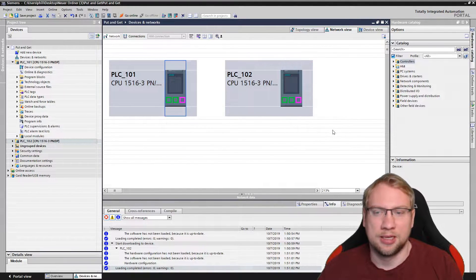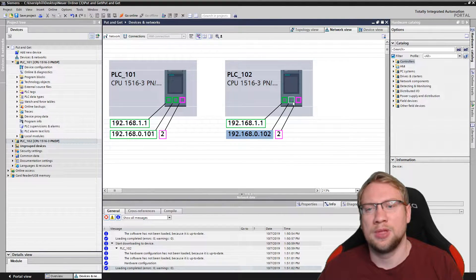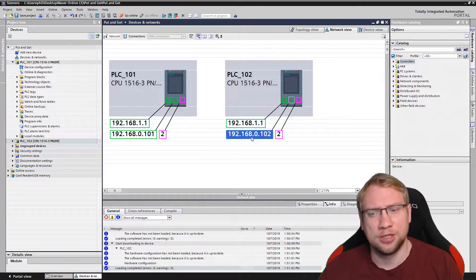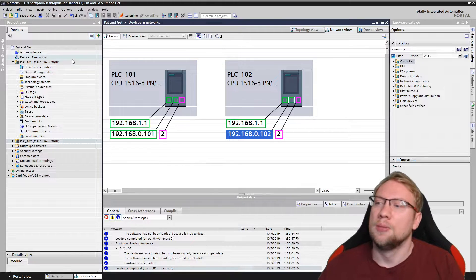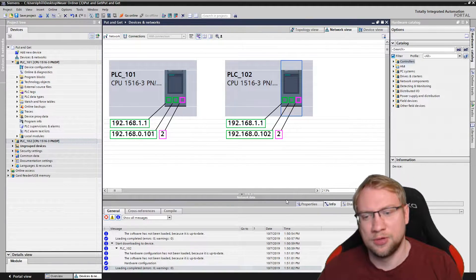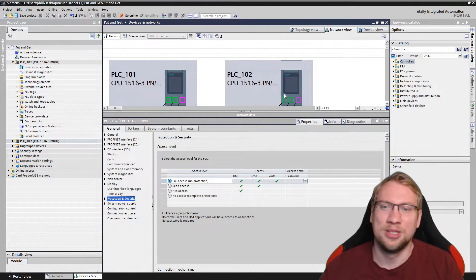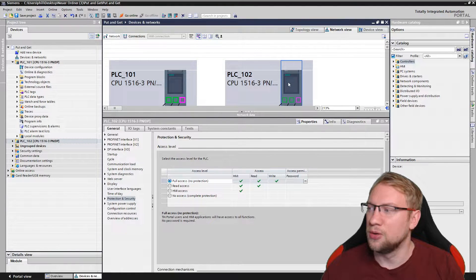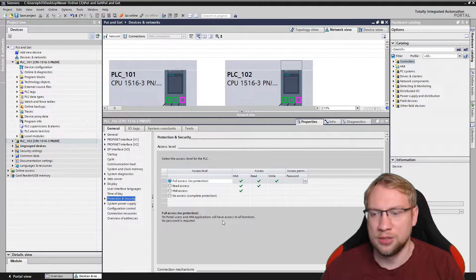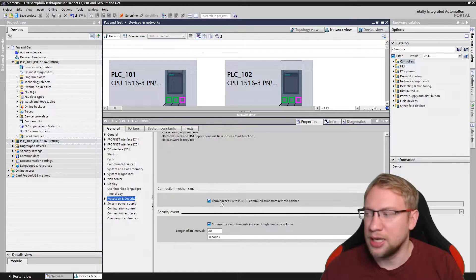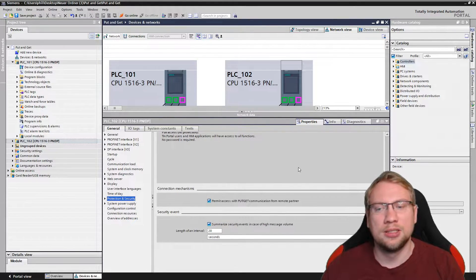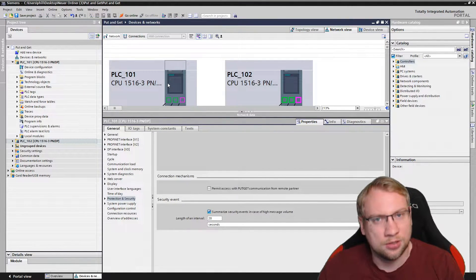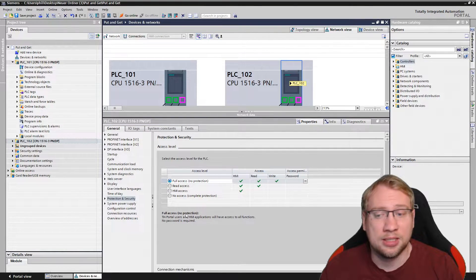We will read data from the second PLC. For this, some preconditions apply as with the PUT command: both PLCs need to be in the same Ethernet network — 192.168.0 is my choice. The second one, the one we want to read from, is 102; the first one is 101. For the second PLC we need to permit access: go to PLC properties, General, then Protection and Security, scroll down, and enable 'permit access with PUT/GET communication from remote partner'. This only needs to be active for the PLC you want to read data from.